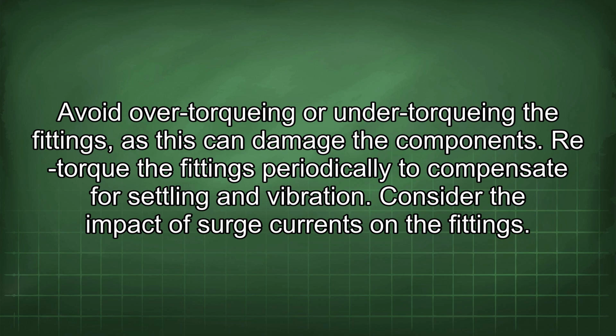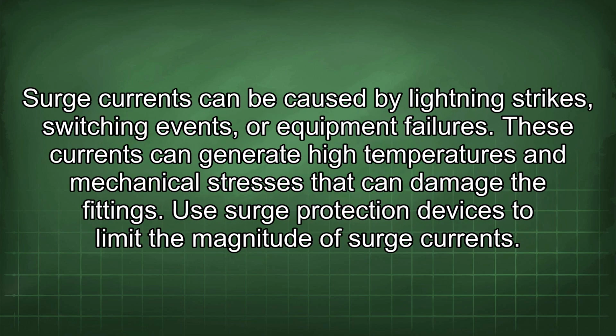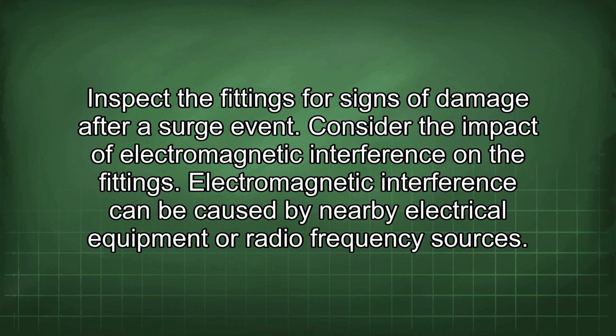Consider the impact of surge currents on the fittings. Surge currents can be caused by lightning strikes, switching events, or equipment failures. These currents can generate high temperatures and mechanical stresses that can damage the fittings. Use surge protection devices to limit the magnitude of surge currents. Inspect the fittings for signs of damage after a surge event.